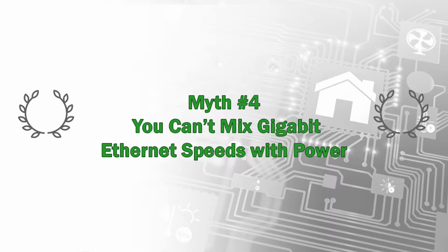Myth number 4, you can't mix gigabit Ethernet speeds with power. Come on, that's ridiculous. All the way through the evolution of the PoE standard, we've been mixing data and power. Now, as data rates increased, what was happening is we're using more and more of those twisted pairs inside the cable. And as power levels increased, we used more and more of those twisted pairs to carry power. But even from the very beginning, you never knew which twisted pair would have data and which one would have power. So you had to ensure that all of them were able to have signal integrity and power transfer.